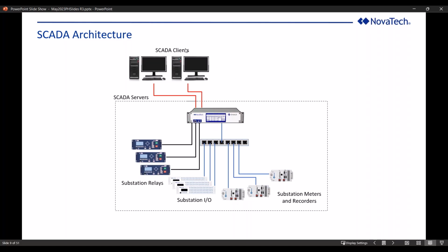In this relationship here, it's different because the control center, your SCADA center, EMS, and so on, will be acting as the client. So it's going to be requesting, polling, and then the data concentrator or the Orion is going to act as the server. We're going to be the DNP3 server that serves up the data.